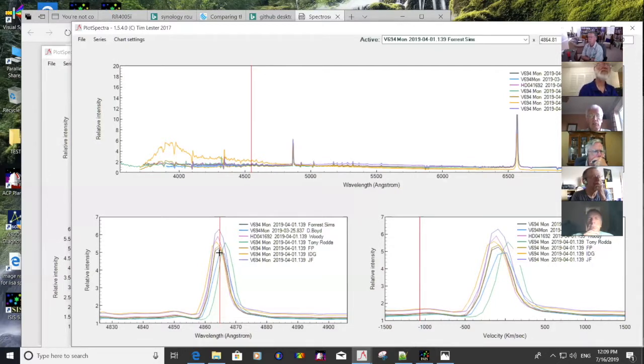The area where we could differ is in the way the wavelength calibration got applied. That's the only thing I can see as a possible area where that could have drifted a little bit between the two solutions. They should all be perfectly in alignment if we've all done it exactly correctly. Yeah, and that's obviously why I came back to this point here, is that we all attempted to do it correctly. What does alpha look like?